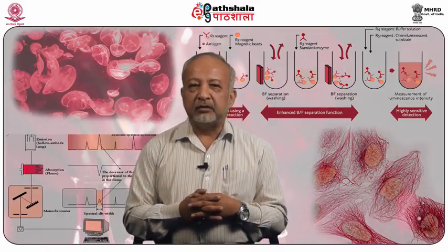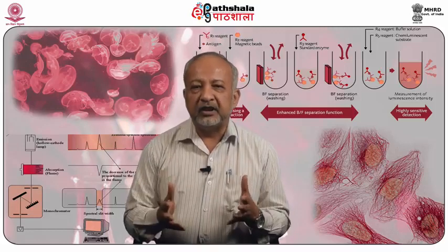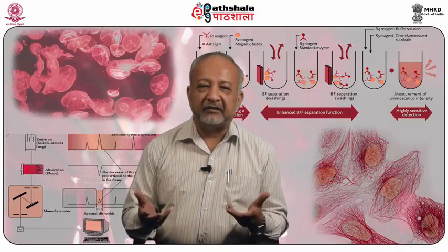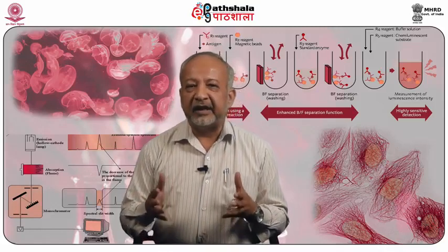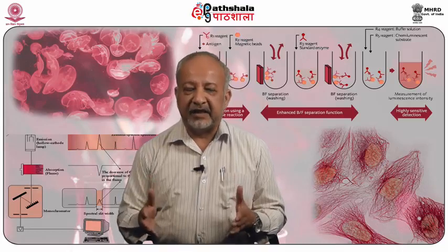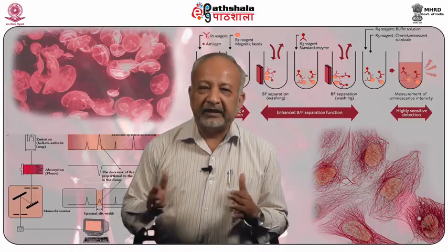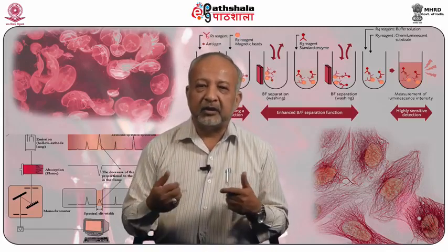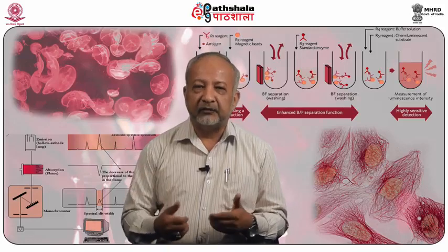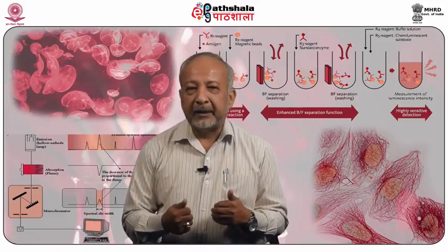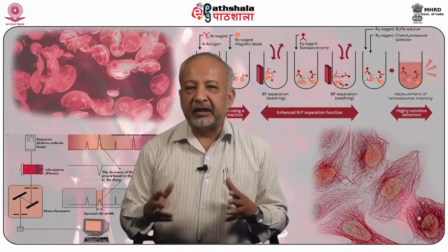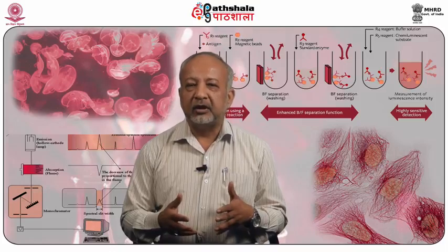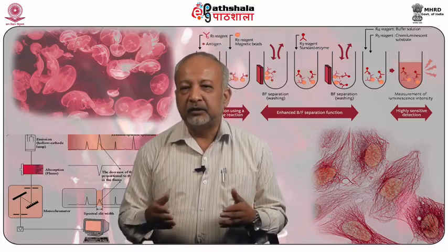However, there are some limitations also, such as they are not well suited for pulsed ionization methods. For example, you have MALDI, which gives you pulsed ionization. They are usually larger and higher cost than other mass analyzers. They are very costly equipment, and that is why gradually they are getting phased out and people are not going for sector analyzers today. Linked scan MSMS gives either limited precursor selectivity with unit product ion resolution or unit precursor selection with poor product ion resolution.